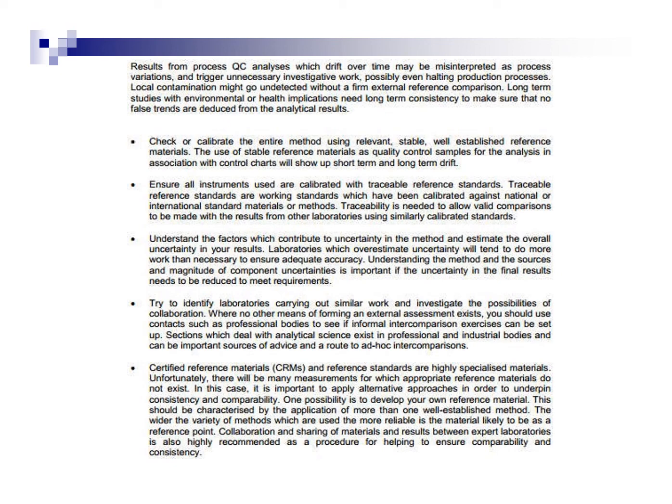Finally, certified reference material, or reference material, or highly specialized material. When we use certified reference material, we can make sure whether the method we are using is right or wrong, because usually the certified reference material comes with the correct value already mentioned on it. So when we use the method to test those samples, we should get the same value as stated in the certified reference material.